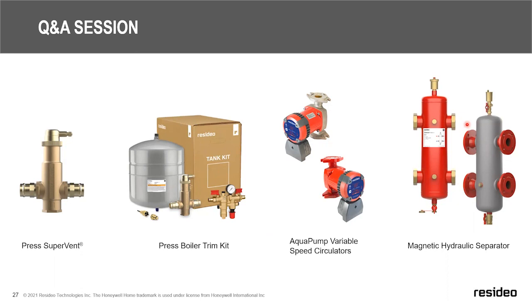It's a much more common problem with zone pump systems, or I shouldn't say problem, it's a more common dynamic with zone pumps, because usually with zone valves, you're going to be matching the boiler output on the circulator. And each of those zone valves is going to allow adequate flow. So we size that pump for maximum flow of the system, which is usually going to be less than the boiler itself.